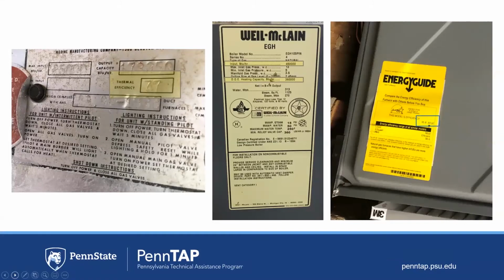The nameplate on your equipment and the specification sheets of your equipment will have information associated with the efficiency of your model. There are a few different ways to communicate the efficiency of your equipment. If the efficiency is not listed on the nameplate, then you can divide the heating output by the heating input for a percent value. You may also see the annual fuel utilization efficiency, or AFUE rating, and this is how efficient the appliance is at converting the fuel into energy to heat your home.